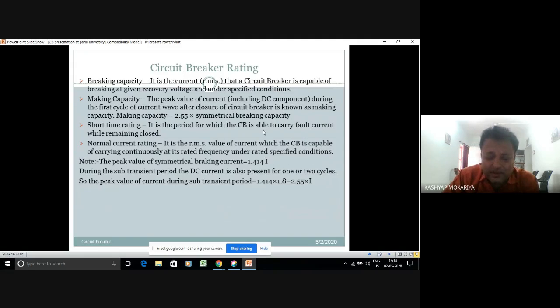Now, in industry, it is very important that you should know what a breaking capacity is. It is the current that a breaker is capable of breaking at a given recovery voltage and under specified conditions. Take an example in industry. If one breaker is of 100 MVA capacity and its service voltage is 33 kV, then 100 into 10 raised to 6 is equal to root 3 into 33 into 10 raised to 3 into the breaking current. Breaking capacity is always given in MVA, and from that the breaking current is deduced.